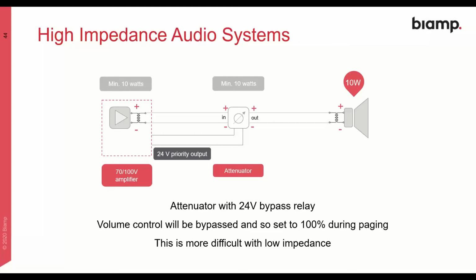So what we have in a lot of our electronics and inside the volume controls is a 24-volt priority output from the electronics, and that is fed to a relay inside the volume control. So when the paging or emergency situation is active, the 24 volts is applied to the relay, and it actually bypasses the volume control, allowing the audio signal to be fed through the volume control at full level. And once again, this is very, very difficult to achieve with low impedance systems. So whilst it's not a factor directly of high impedance systems, it's something that comes out of it because of the systems that are available around the infrastructure.